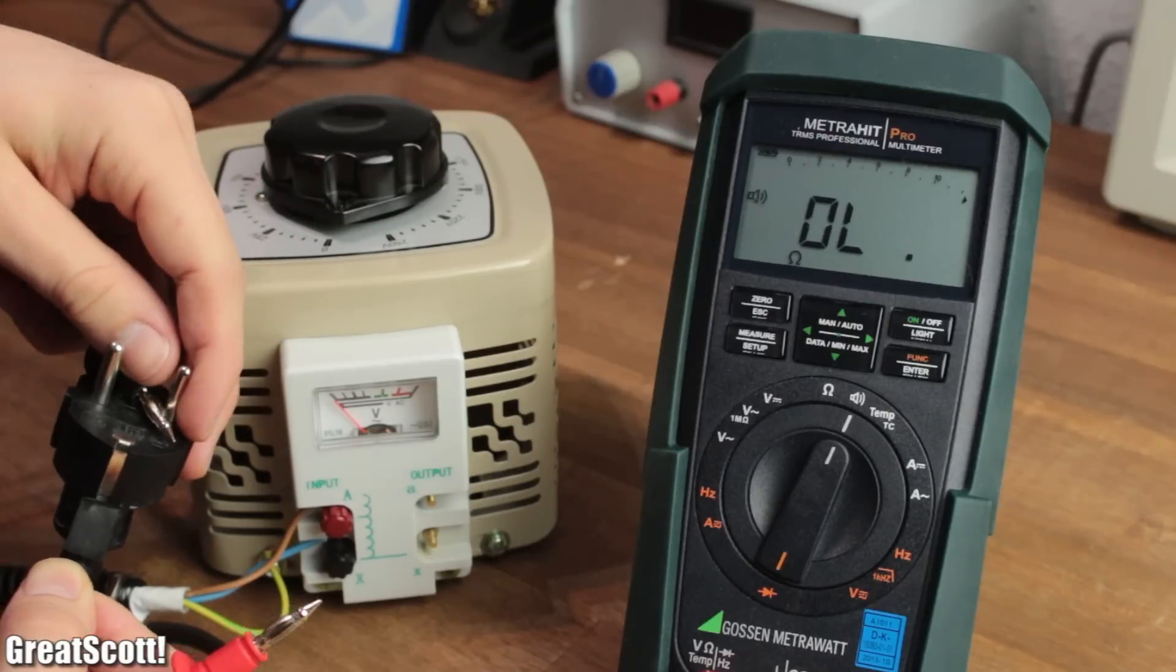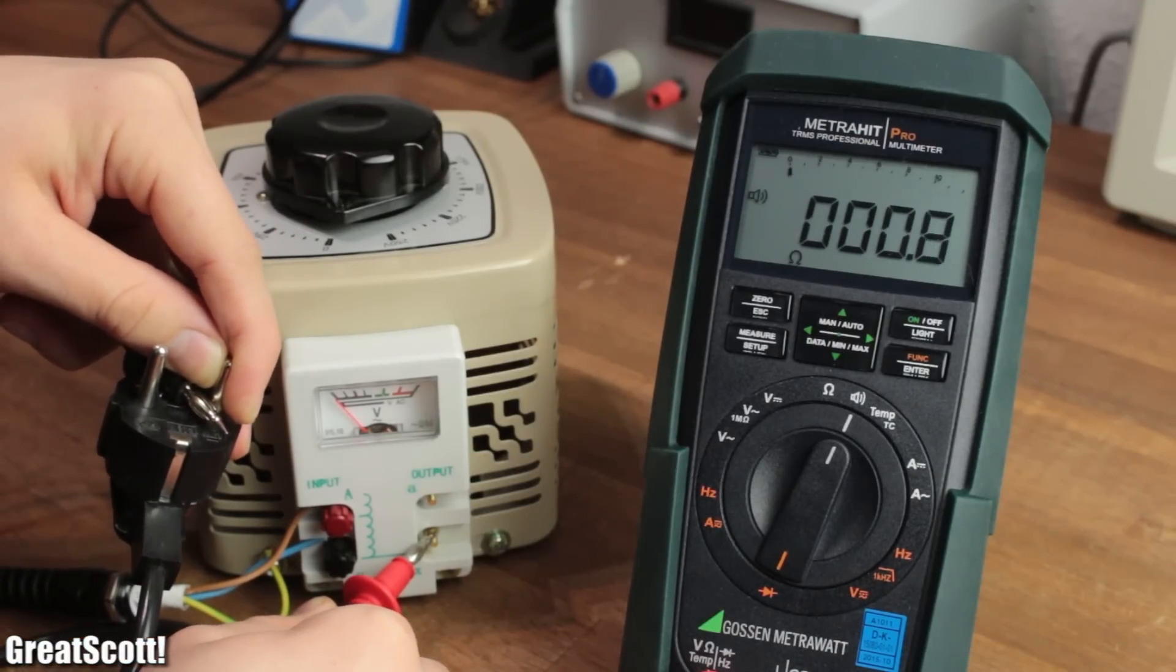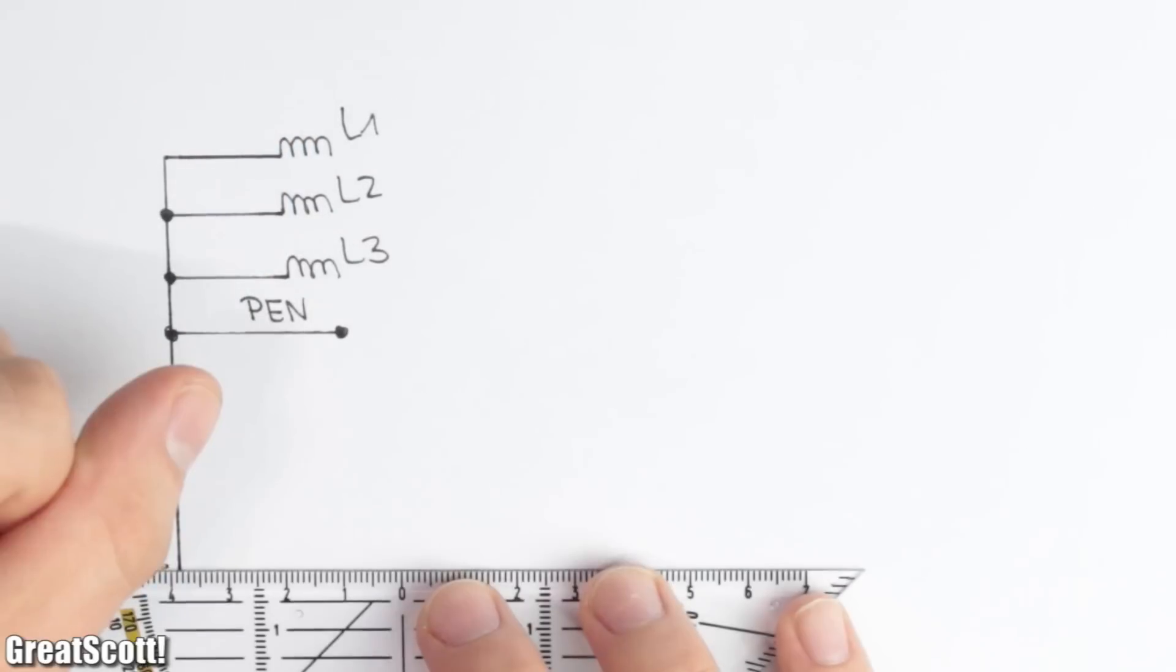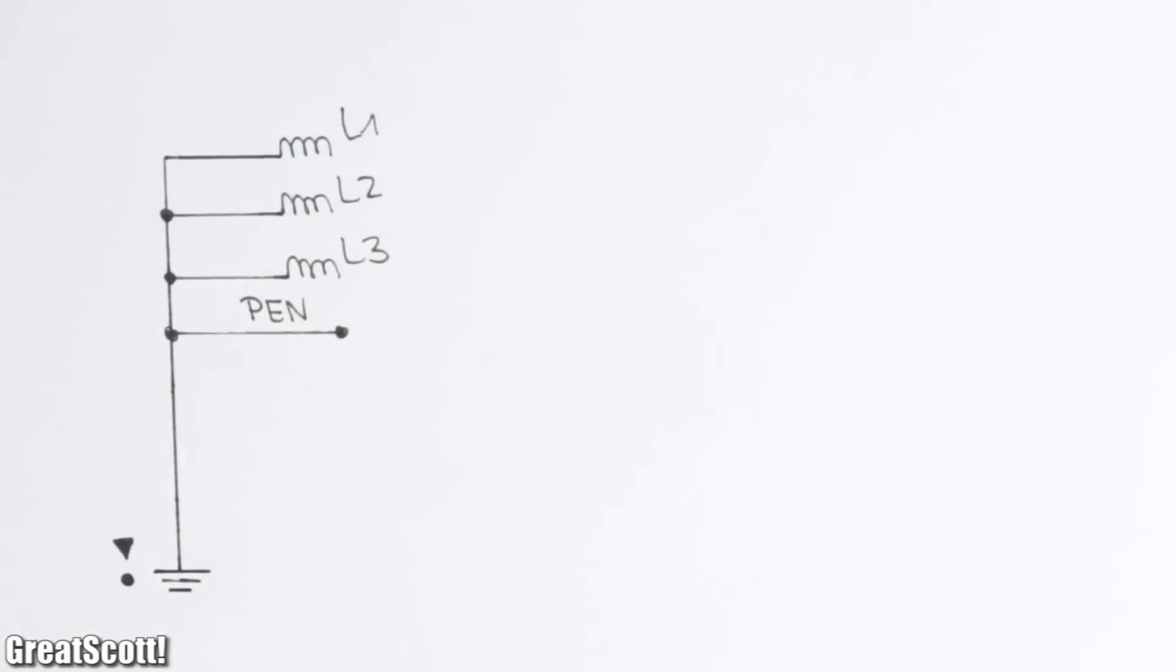The only problem is that the input and output is not galvanically isolated. This can be a problem with the TNCS low voltage grid that is available here in Germany. We got three live wires and a combined protective and neutral wire. But the important thing is that the star point of the supply transformer is earthed.